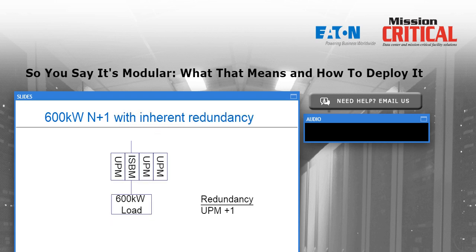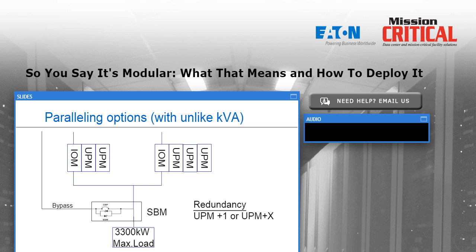However, we would recommend that be contrasted to what we see here, which does the same thing in terms of redundancy. Here we have 1 UPS, and it's got a total of 3 300 kilowatt UPMs. The ISBM segment in the middle there is the tie cabinet that ties them together. 600 kilowatt load, I've got 3 300 kilowatt UPMs. Any one of them needs to be taken off for service or shuts down due to failure. The other remaining 2 UPMs continue to support the 600 kilowatt critical load, so I have that N+1 redundancy without buying a second UPS and battery system. Very attractive value proposition for a lot of our clients.